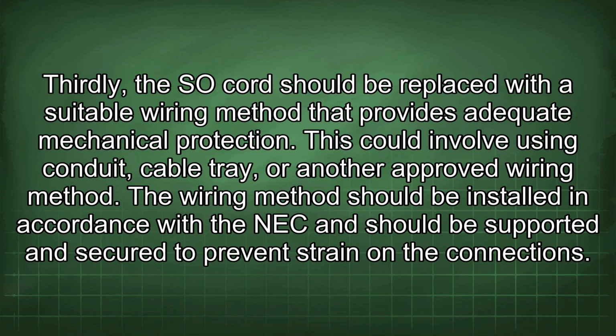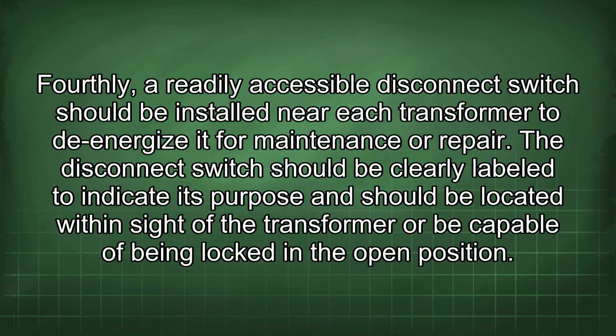Thirdly, the SO cord should be replaced with a suitable wiring method that provides adequate mechanical protection. This could involve using conduit, cable tray, or another approved wiring method. The wiring method should be installed in accordance with the NEC and should be supported and secured to prevent strain on the connections. Fourthly, a readily accessible disconnect switch should be installed near each transformer to de-energize it for maintenance or repair. The disconnect switch should be clearly labeled to indicate its purpose and should be located within sight of the transformer or be capable of being locked in the open position.